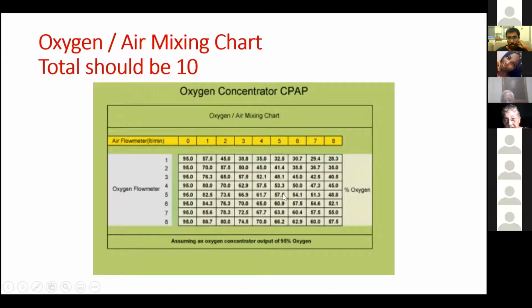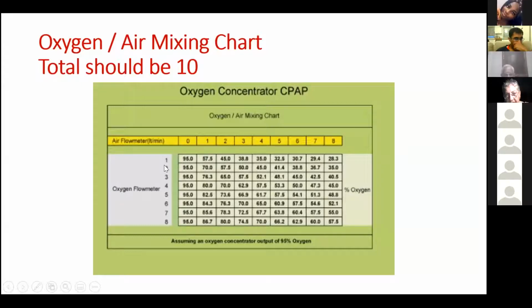If the baby's saturation is good, high, and we want to decrease the amount of oxygen given to this baby, we will have to increase the amount of air and decrease the amount of oxygen, such as from the 57, let's say we want to move to 50, we'll put air on 6 and oxygen on 4. So this way we will go weaning, going for more air and less oxygen. And if the baby is deteriorating, then we do give more oxygen and less air. When we give 0 oxygen, then the baby will be in room air. If we give 8 oxygen and 0 air, the baby will be in 95% oxygen.